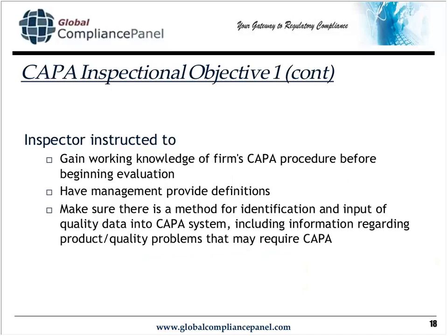The inspector is also going to look at your CAPA procedures. Gain working knowledge means just read your procedure. And anything that's vague, any kind of definitions, they're going to ask you about. And your procedure should also have in it what data you identify and input into the CAPA system and how you get that data.